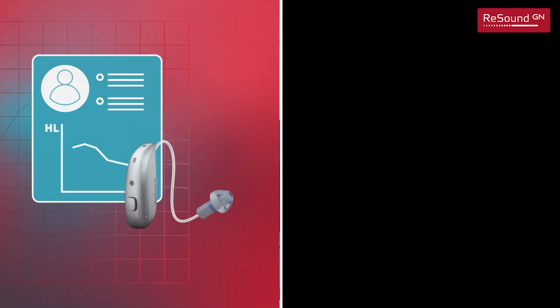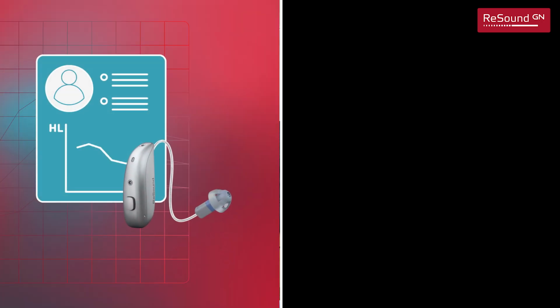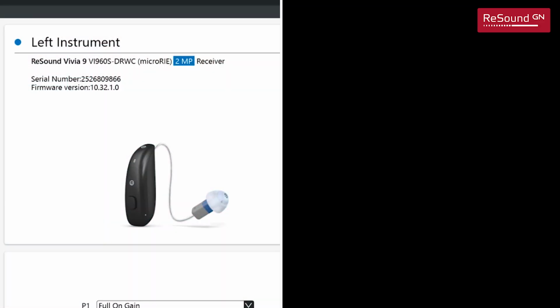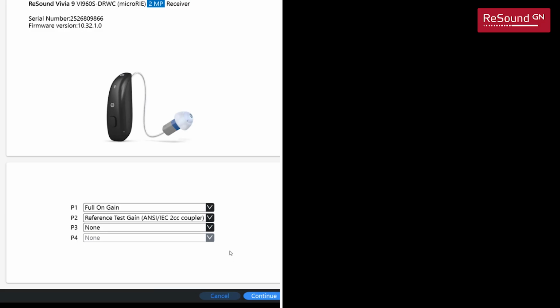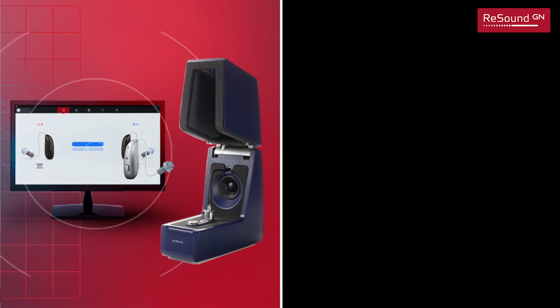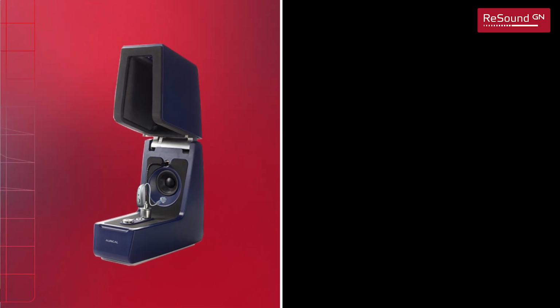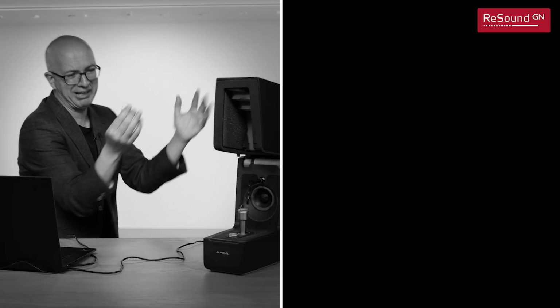What? Yep, you had to delete all your client's programming because instead you had to configure the hearing aids for whatever test you want to run in different programs. Normally like this: full-on gain in program 1 and reference test in program 2 according to the standard that you want to use. Click Save, and from here you are no longer connected to the fitting software. And the first thing you experience is that the hearing aids will start squealing because they are programmed with full gain and there is no easy way to mute them.